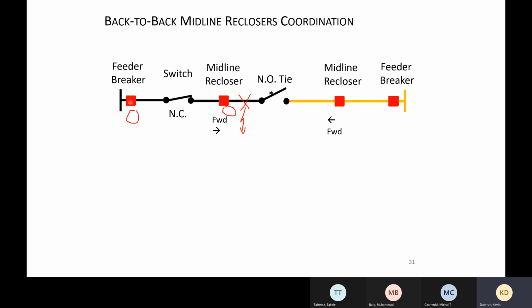And our system operators and area engineers always bring it to us and say, hey, you guys miscoordinated. What we were able to determine was this was fault 1. Then there was a subsequent fault from slapping conductors somewhere between the midline and the station breaker. The way we can tell is that fault current goes down as you go farther out on the distribution feeder, because of the impedance. This fault was 1,000 amps. The subsequent fault that actually locked out the feeder breaker was 5,000 amps, which means it was a totally separate fault and a whole lot closer to the substation.